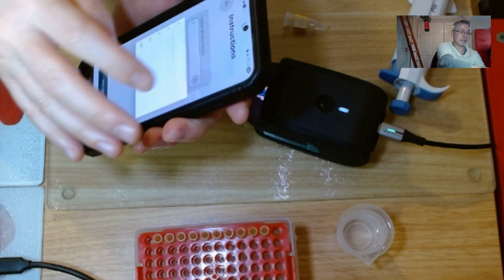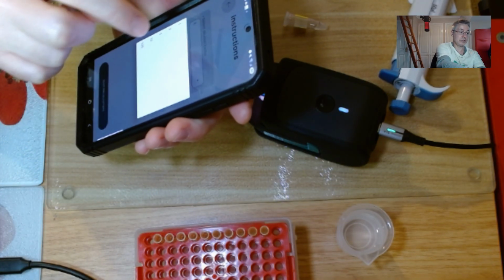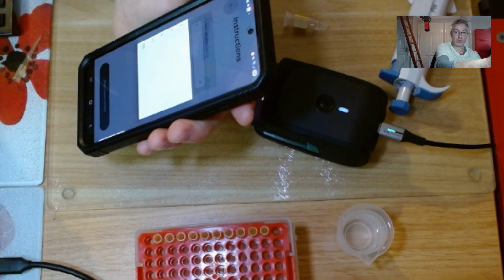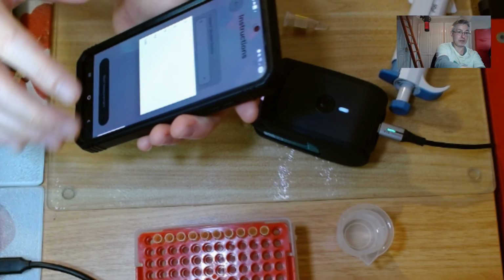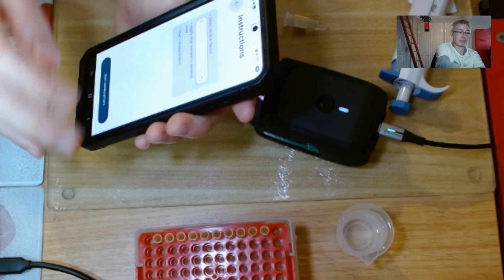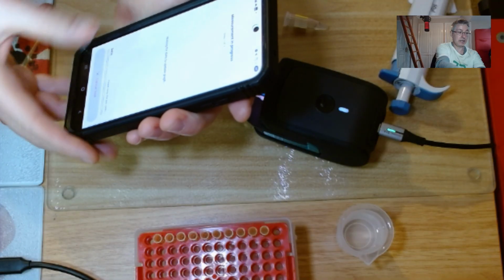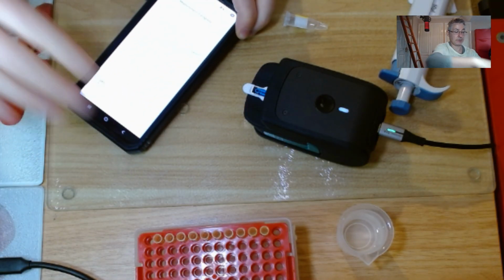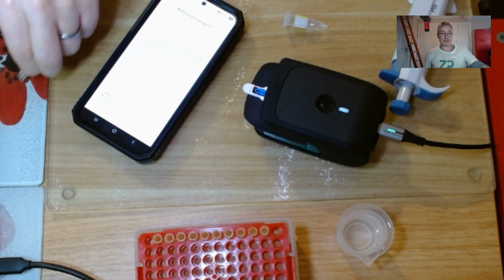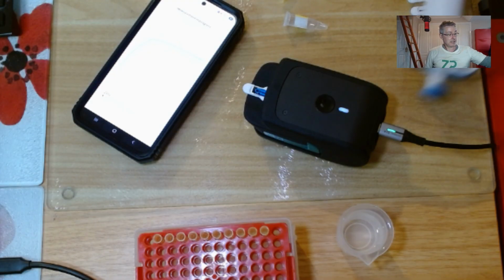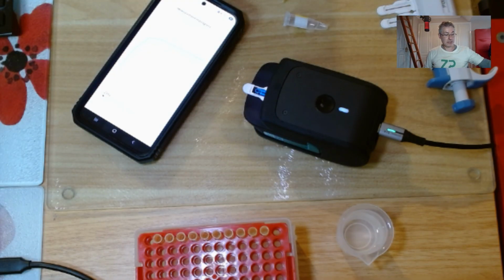I will drop down the menu and tell it that this is a 1-in-2 dilution, because I've taken 1 volume of the sample, 1 volume of the buffer. I will talk about the dilutions a bit again in a minute. And now that's started. So it says here 2 minutes 42, 2 minutes 40. So yeah, it's a 4 minute assay. It's definitely a less than 5 minute assay. So off it goes now.